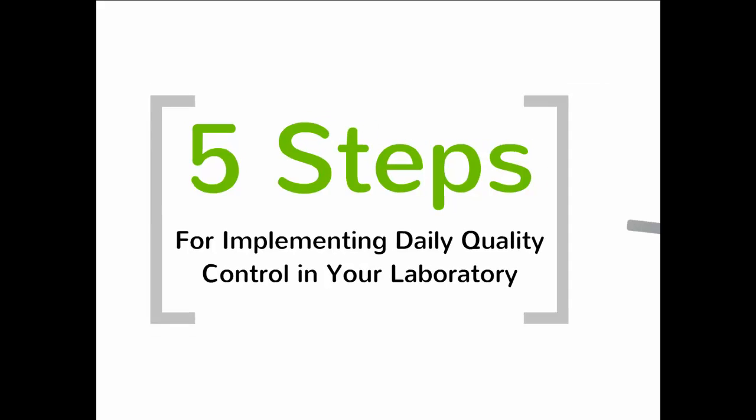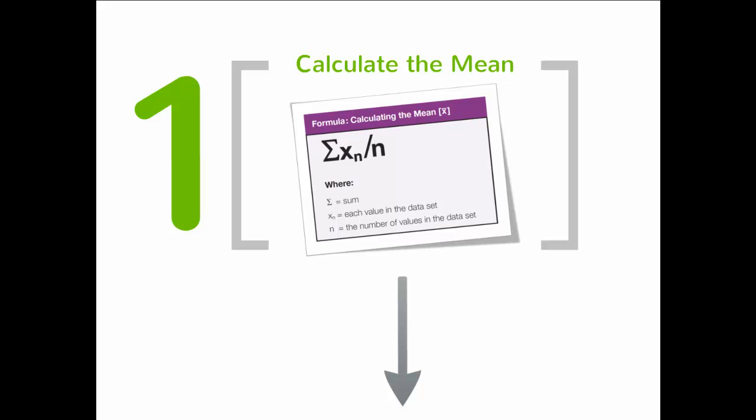Let's look at five steps to implement daily quality control in your laboratory. Step one is calculating the mean. The mean, or average, provides the best estimate of the analyte's true value for a specific level of control. I encourage you to take a look at our video for calculating the mean if you need more information.